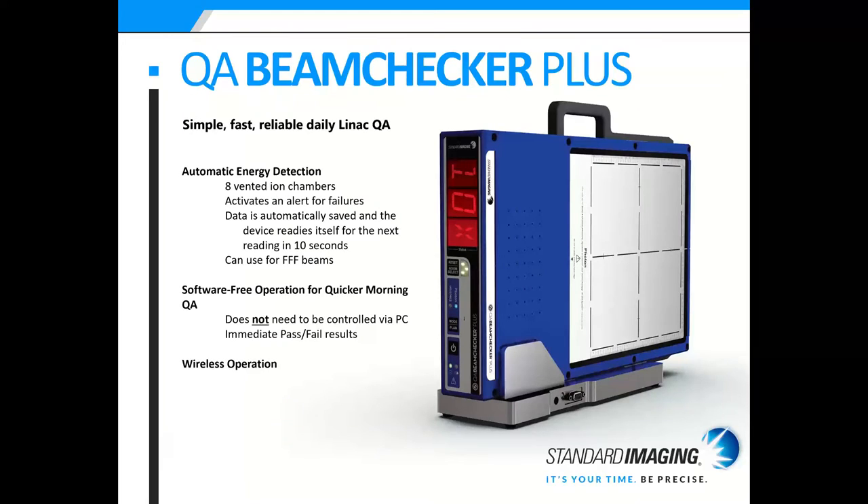I'm going to start with our daily QA solutions. For daily QA, we have the QA BeamChecker Plus, which is a simple, fast, reliable daily linac QA tool. It's super easy to use — you just place it on your couch for either the photon or electron side, deliver your 100 MUs, and on the screen it will flash the energy you just delivered. It has eight vented ion chambers. If something is ever wrong with either the device or the linac, it will flash a failure code so a physicist can detect and address the issue sooner. The data is automatically saved and the device readies itself for the next reading in 10 seconds, and it can be used for FFF beams.